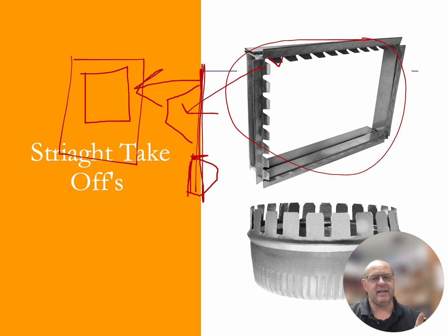Remember, anytime that you have a gap, you're going to want to put mastic on it as well. That way we can seal that up. Now, there are going to be drive cleats that we're going to be able to put on this takeoff assembly. There's also going to be S-lock on it that we can take that square duct and put on there. There are transition takeoff assemblies, which go from a smaller size into a larger size. And there are also round and square-to-round types of takeoffs as well on our systems.